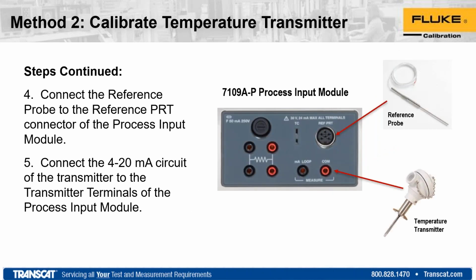All right, so this is just pretty basic. We're inputting the reference probe. The other nice part about this process option is it utilizes what we call our InfoCon technology. So the actual connector for the reference has an IC in it that's programmed with the probe constants. Once you connect it, it self-recognizes, so you don't have to do additional programming like you do in some of the readouts. The next step would be to take some leads, connect to the loop COM ports, and then on that little transmitter head, typically you just unscrew that.